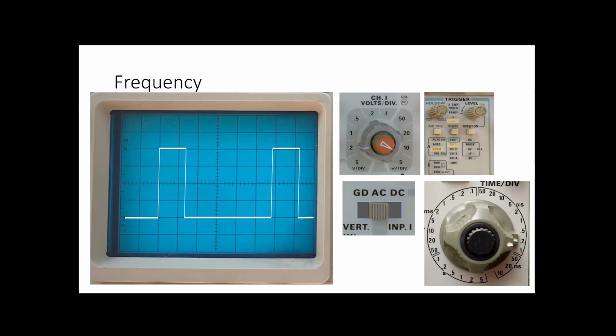So I'm measuring, let's say, from the top left-hand corner to the top left-hand corner, or the bottom right-hand corner to the bottom right-hand corner. It doesn't matter, as long as I measure from the same point on the waveform to the same point in the waveform. If I get it as big as I can on the screen, then I get the most accuracy. If I try to measure something and it's a tiny wee picture, then I'll make a guesstimate and it'll be a factor of 2 out. Whereas if I make it as full screen as I can, I get the most accurate measurement.